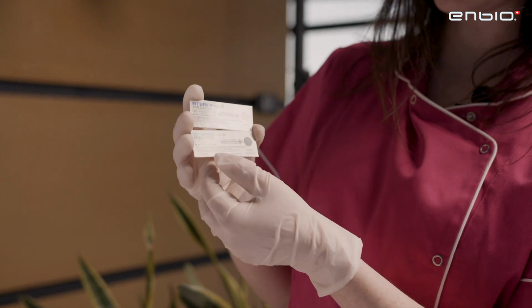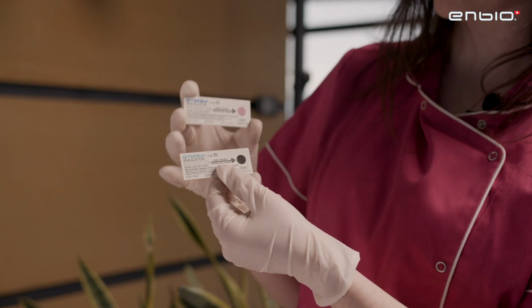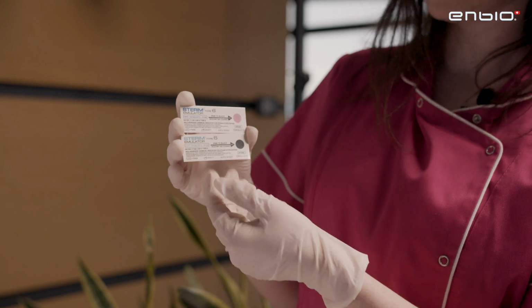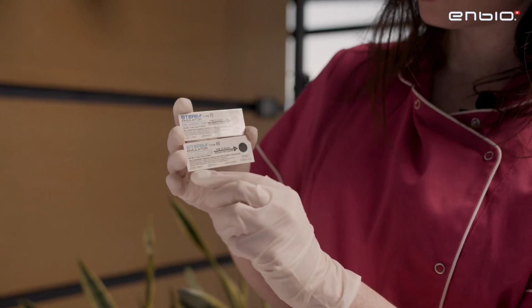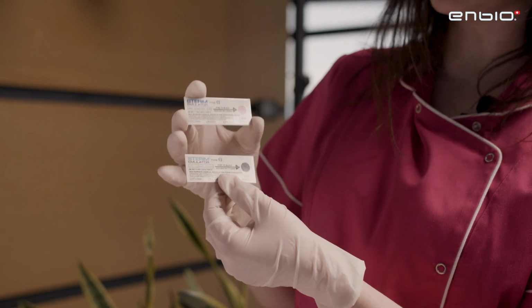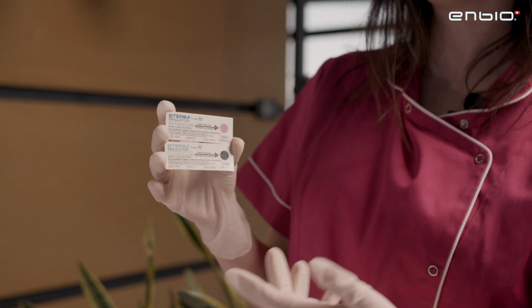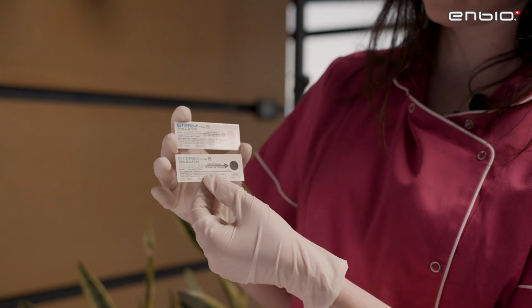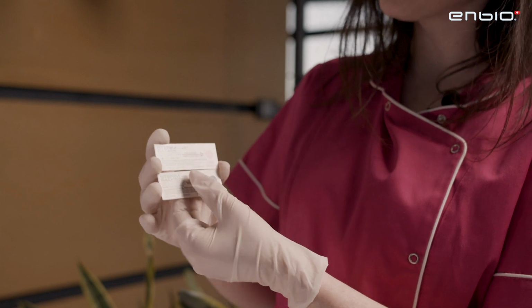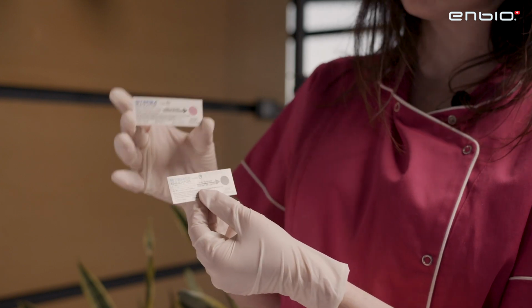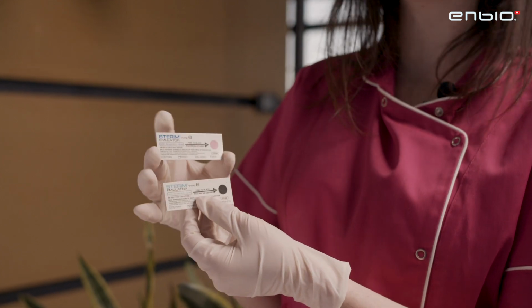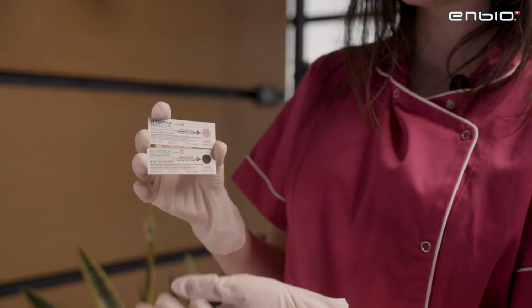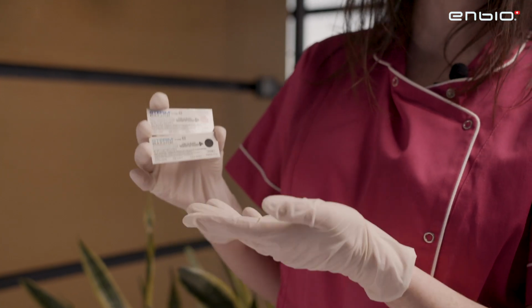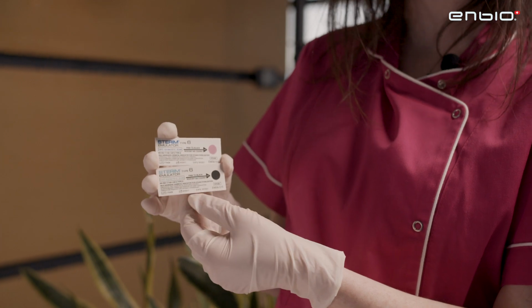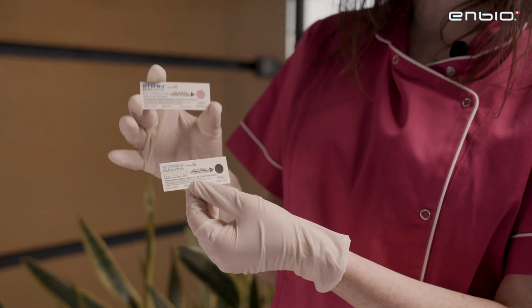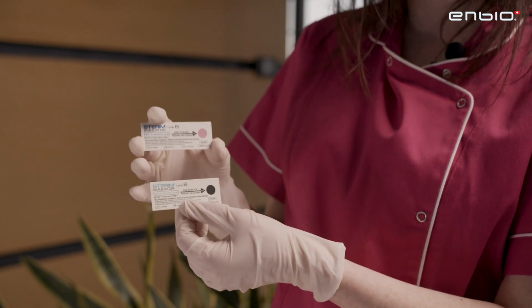We can see here the technology of the sterilizers that we are using. So these tests are to be done with a steam sterilizer, and we can see the time that the sterilization test needs to be inside the autoclave so that it confirms the efficiency of the sterilization process. And we have to remember that one of these test indicators has to go inside the sterilization pouch with the other instruments that we have inside the pouch. And if, for instance, we are using different sterilization pouches at one time, it is enough to put this indicator only in one pouch and not in all of them.